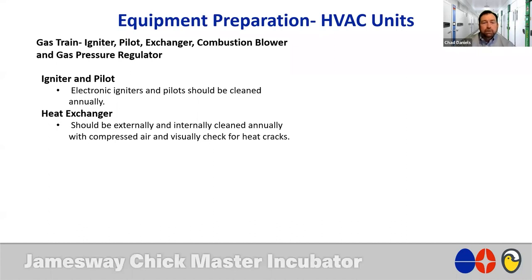Because if you have a heat crack or any type of damage to that heat exchanger, the combustion of the gas then is allowed to essentially put carbon monoxide into the airstream, and then that's going to be provided into the hatchery with the fresh air. So make sure you do a visual inspection of these heat exchangers to make sure they don't have any damage.